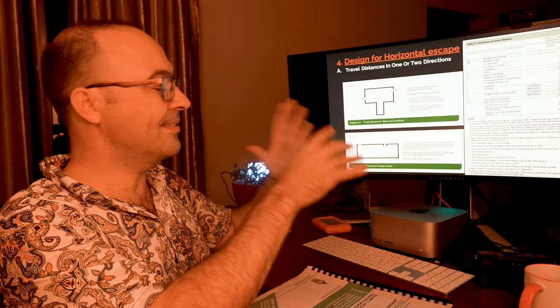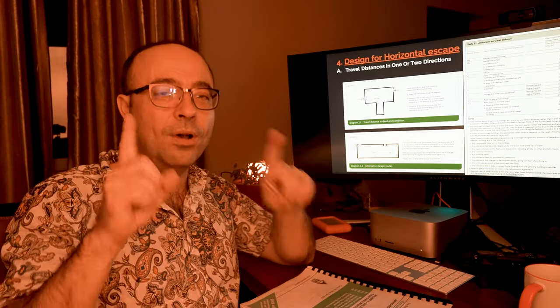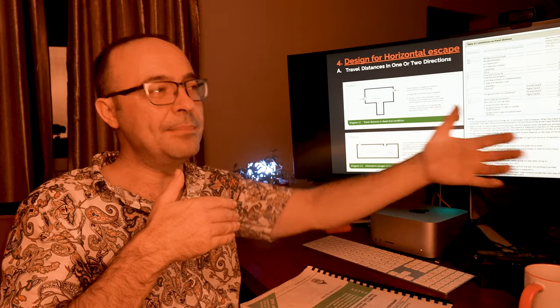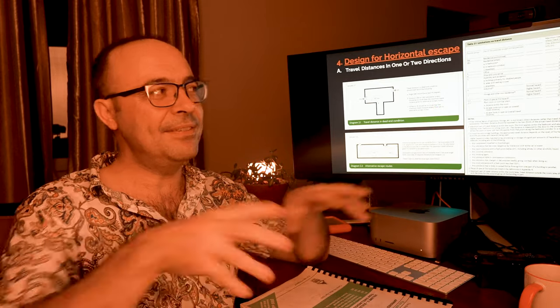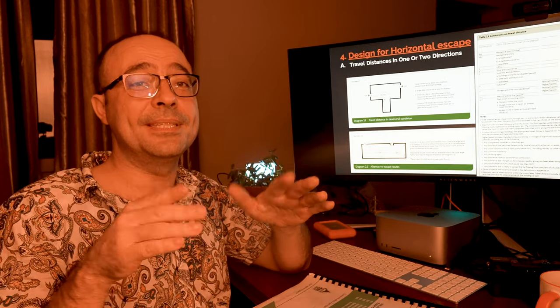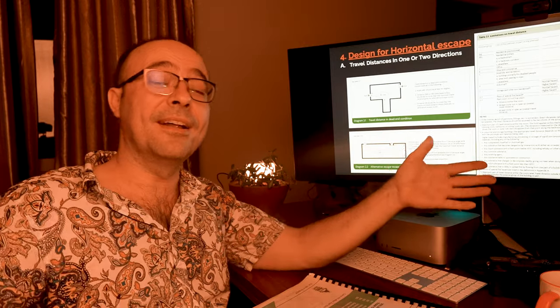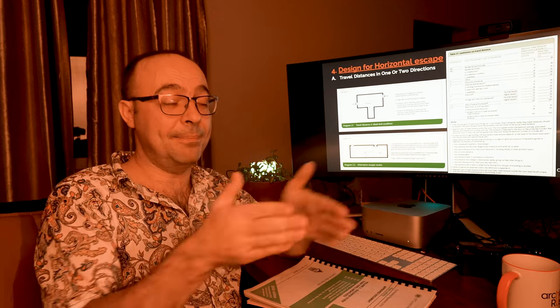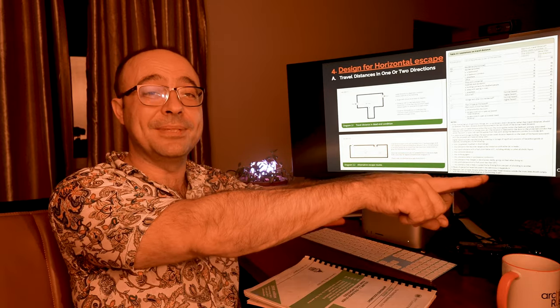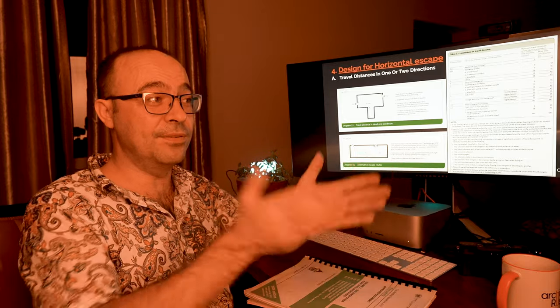Designing for horizontal escape — this is on the same floor. This is one of the most important things for fire escapes. If you've got one fire escape, you've got to be no more than 18 meters from that escape anywhere on the floor. Even standing in the corner of the building, you can't be more than 18 meters away. Now if you've got two fire escapes, you can go up to 45 meters to that fire escape, but you've got to have a point of choice. There's got to be one on each side, and the angle needs to be more than 45 degrees. You can't just put two fire escapes right next to each other — they have to be 45 meters distance and 45 degrees or more.